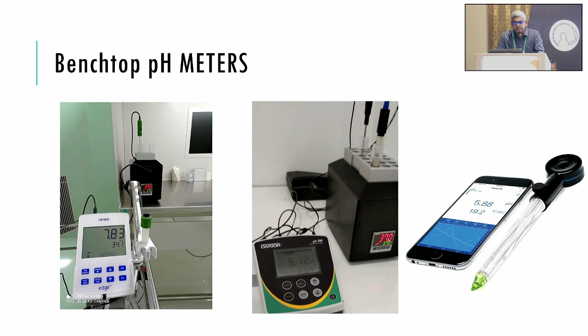There are many methods to measure the pH. The most common ones are the benchtop pH meters. I don't have any special interest in any of these pH meters or any gadgets which I show. That's a disclaimer. These are some of the pH equipment which I have used in my experience. Some hospitals and centers use ABG machines, even handheld machines, and it works well for them. And there are also online pH meters. These are more expensive but very accurate, and can avoid the pH drift that the other equipment have.